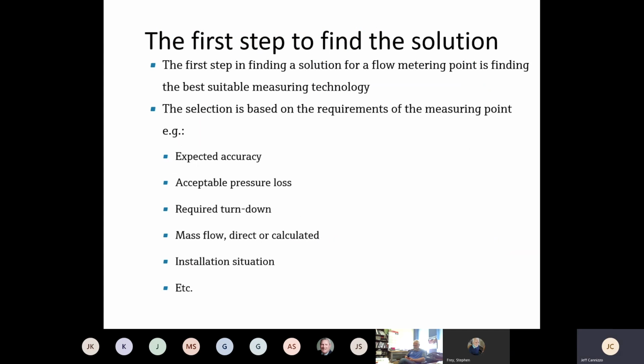So you have to find a flow meter. So the very first step is determining what type of measurement technology is the best. So there's different requirements that kind of help you steer towards the correct technology, the best technology for your application. Not in any particular order. What type of accuracy do you expect? What type of pressure loss will the meter create, and what can you live with? What's your required turn down? So how high do you need to read, and how low do you need to read within a certain accuracy? We're going to talk a little bit about this with one of the other meters. If you need mass flow, do you want to do it directly, or can you calculate it?